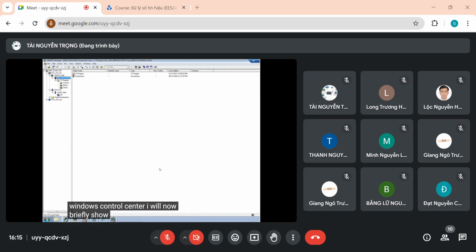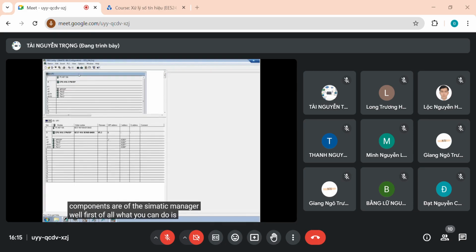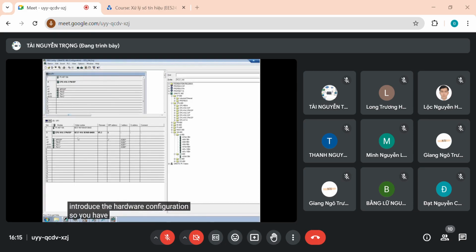I will now briefly show you what the different components are of the SIMATIC Manager. Well, first of all, what you can do is introduce the hardware configuration. So you have to choose a CPU, right? Here we're working in simulation, so I've just added a CPU. In reality, of course, you'll have to interact with the system, so there might be several CPUs, and of course there will be I/O, so you'll have to choose some of these cards: analog input cards, analog output cards, digital in and digital output cards. Once you have done this properly and that you have compiled things and downloaded to the relevant CPUs, well, you can interact with the actual system.